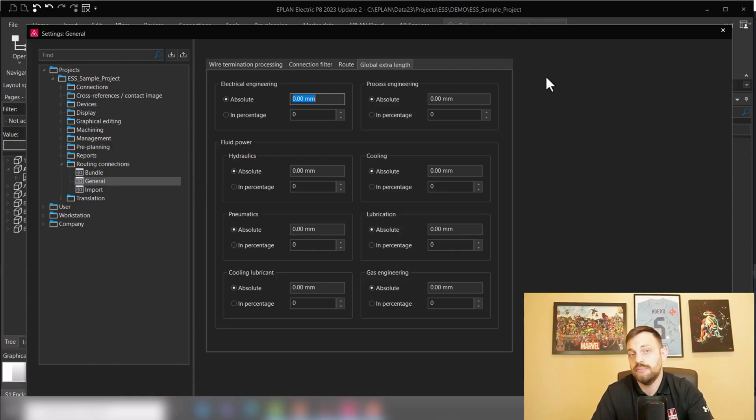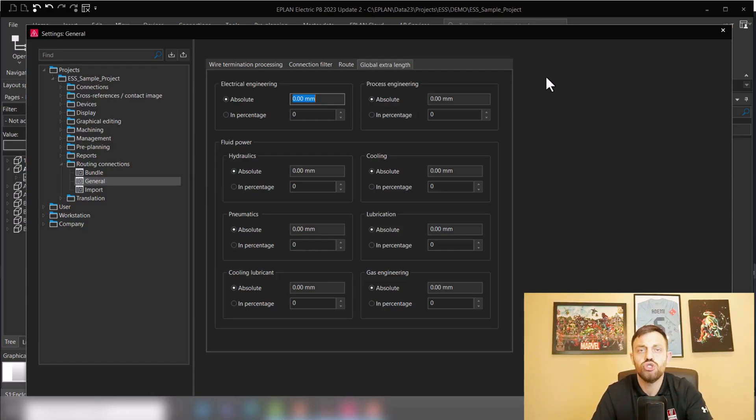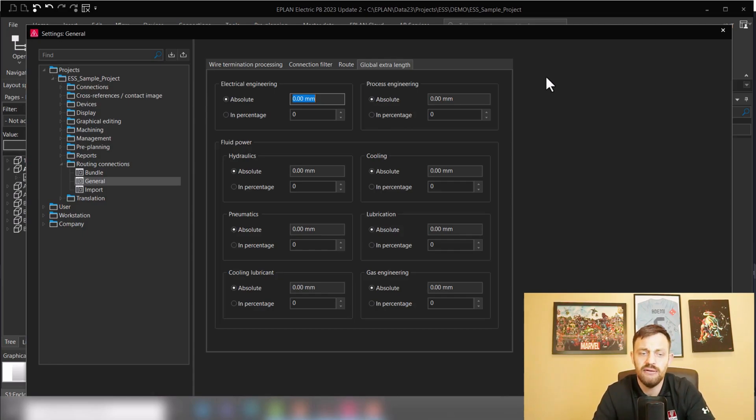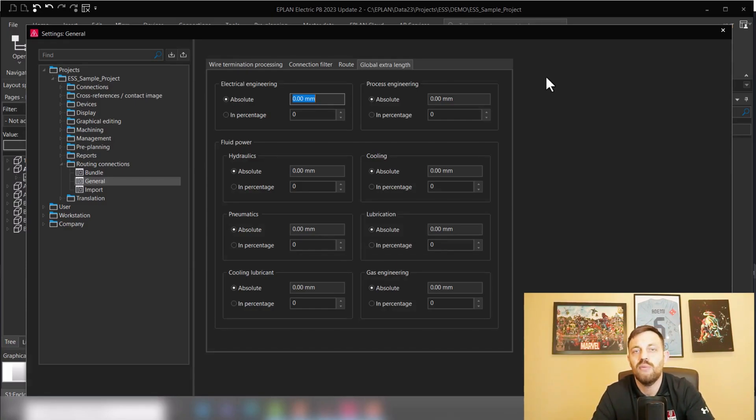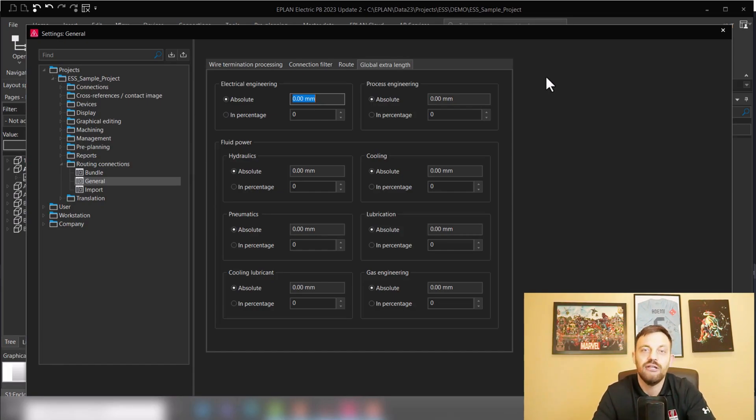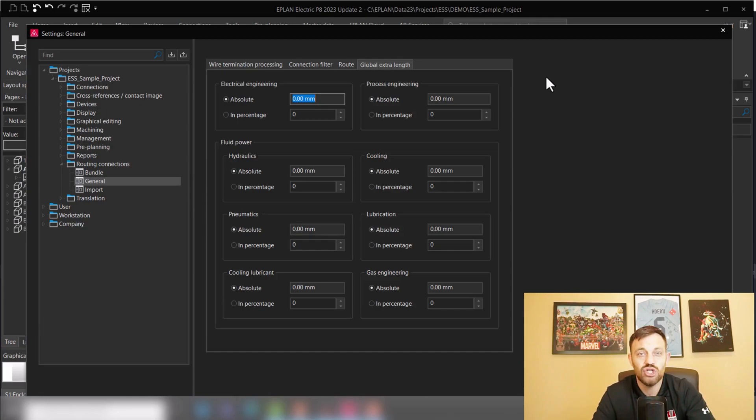You can add an absolute value in millimeters or an inch, and every wire then will get this additional length. Or you can choose a percentage, for instance 3% or 5% extra length, and then every wire will be automatically by this value longer. So these are the three ways how you can add additional length in EPLAN Pro Panel.